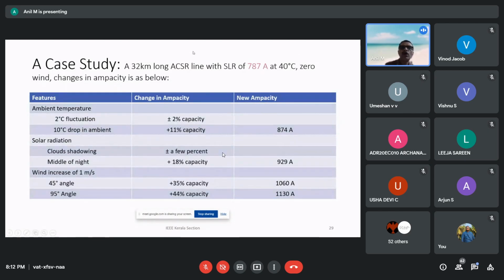So this is a case study with a 32-kilometer ACSR line with a static line rating of 787 ampere. That's decided by the thermal overloading capacity of the conductor at 40 degrees Celsius, zero wind. Changes in ampacity are as given in the table. Features ambient temperature: if there is a 2 degrees Celsius fluctuation in ambient temperature, the ampacity change is plus or minus 2% capacity. A 10 degrees Celsius drop in ambient temperature yields an 11% increase in capacity. That is, the SLR of 787 gets increased to 874 amperes. That's the new ampacity in case of a 10 degrees Celsius drop in ambient.